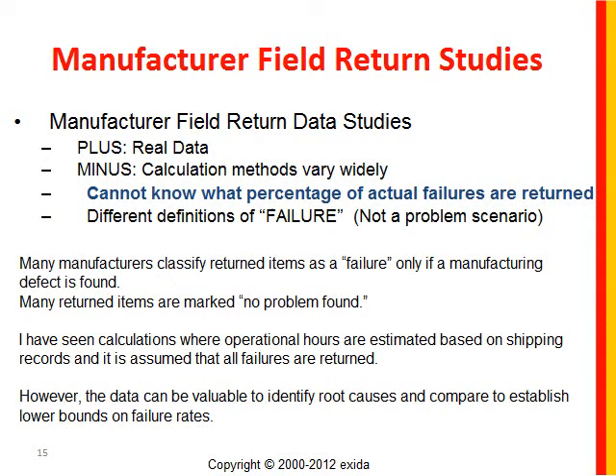Manufacturers gather warranty return information, and that can be a useful source of failure information. At exida, when we do a certification of an existing product, we always study the field returns to look for potential problems and make sure a manufacturer's product is sufficiently safe for a given SIL level. So we get to see a lot of manufacturer field return studies and use them for comparison and verification purposes. However, most manufacturers — including myself when I was taught how to do this — mark many problems as 'no problem found.' So you really have to be careful about the absolute failure rates, but this data can be valuable to identify root causes and compare.